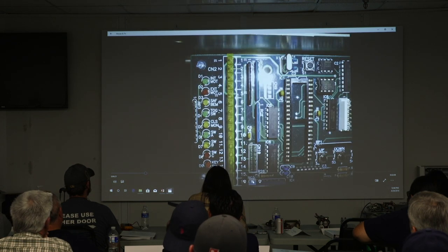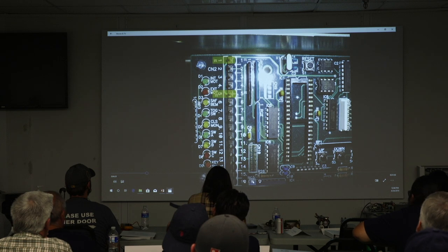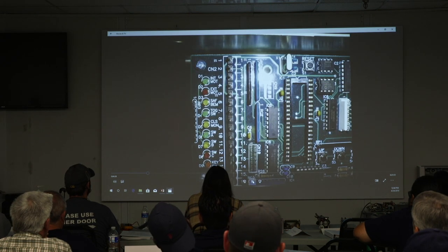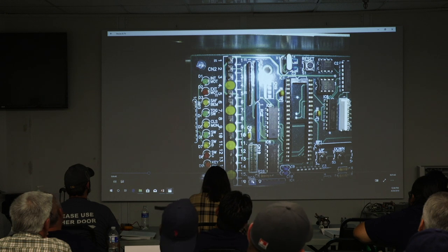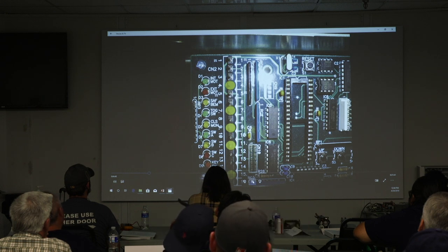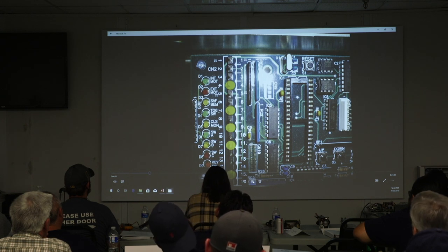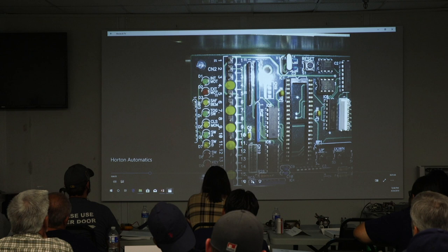Most of the inputs on the C2150 are connected to and powered from the 16 terminals at CN2. 24-volt DC is available at pin 1 and pin 5, and is marked with 1 long and 2 short dashed lines. All common connections are marked with a trailing decimal point. Pins 4, 7, 9, 11, and 15 are commons, and are electrically the same. They can be used as negative terminal when providing power for accessories, or they can be used to complete the circuit for the inputs. Everybody get that?